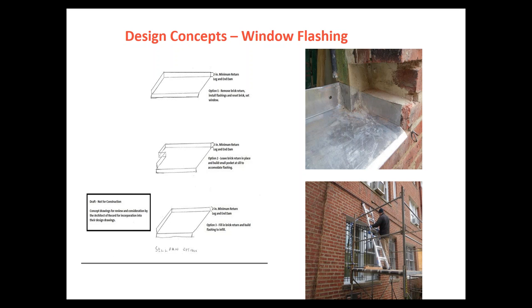Something that might come out of this on an existing building is something critical for a window replacement program. We see these on commercial, residential, and federal buildings. Window replacements are becoming more common — a building in pretty good shape can be a good target for energy improvement. On a current project with mass masonry walls, replacing single-pane steel windows with new windows provided a 300 percent improvement of the window opening performance, and a 100 percent improvement of the overall energy performance of that building. We find this as low-hanging fruit sometimes. One thing to work through is flashing concepts — we provided a series of options with a nice soldered flashing accommodating some existing structure that would have been challenging to modify.